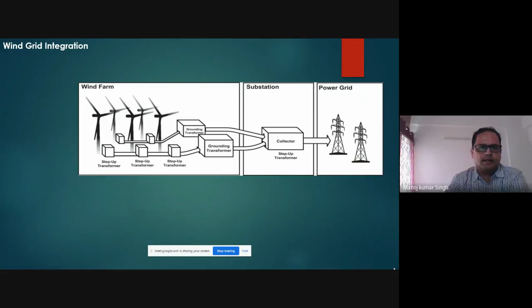On the grid integration side, turbines generate power at 600 to 650 volts. That power is stepped up at the unit transformer to 33 kV or 22 kV level. These 33 kV lines are connected to a pooling or collector substation and get further transformed.